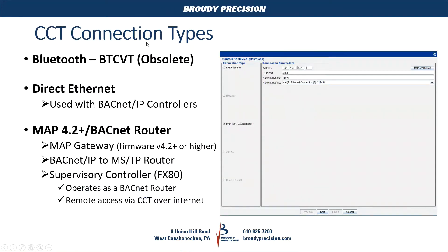To get started, I want to talk about connection types. When you're in CCT, this is the screen that comes up when you want to download, upload, or commission controllers. You'll see the types on the left. What we're going to be working with are typically the BACnet router or the MAP gateway. There's also, for those that still have the old BTCVT Bluetooth adapter, you can use the Bluetooth type. There's Zigbee if you're doing wireless, and Direct Ethernet if you're doing BACnet IP controllers. Today we're going to concentrate on BACnet router and MAP gateways.